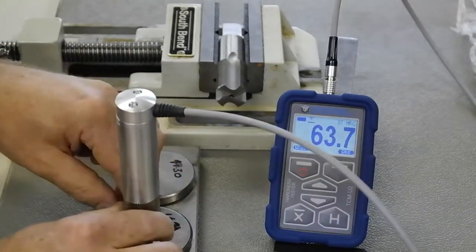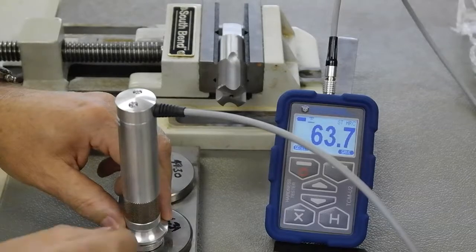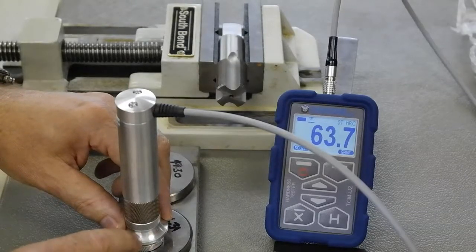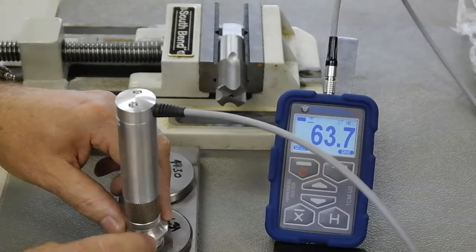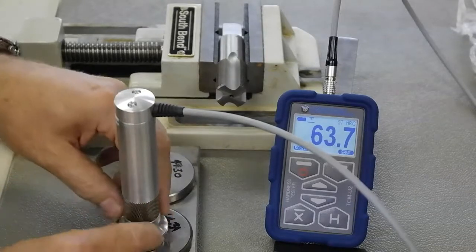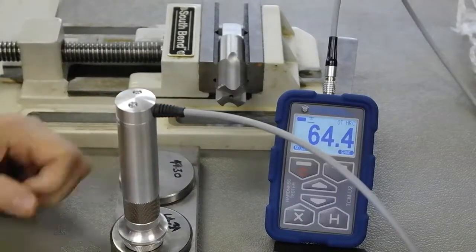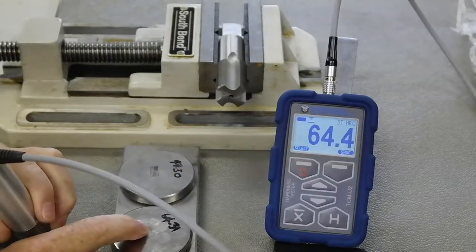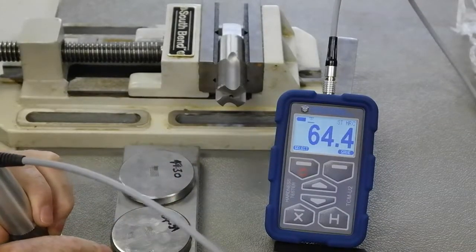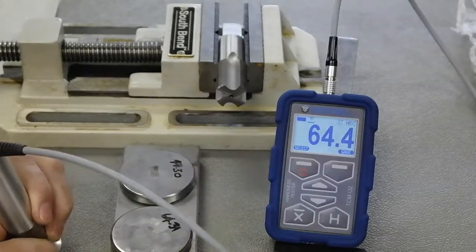63.7. I've got the device set up now so that every test that I do is the actual result. I can also set it up to do averaging. So if you do three tests it's going to give you the average of those three tests and give you an even more accurate result. So you can see here the test block is 64.3. Its tolerance is plus or minus 0.5. We're right on the money.